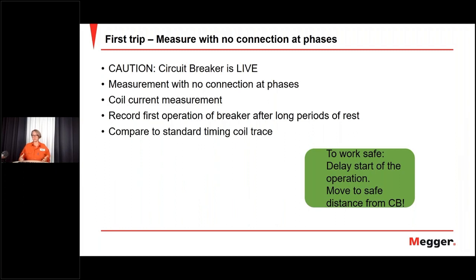What should we consider here? Yeah, as I said, the circuit breaker is live, be aware of that. And to work safe, I would recommend to delay the start of operation so that you can move out of the way. You can stand 100 meters away, just put a delay and you can walk out of there.